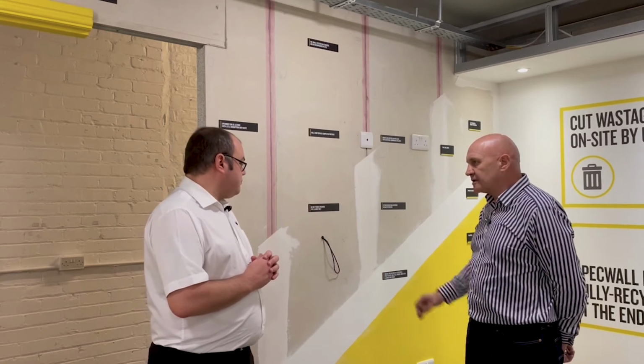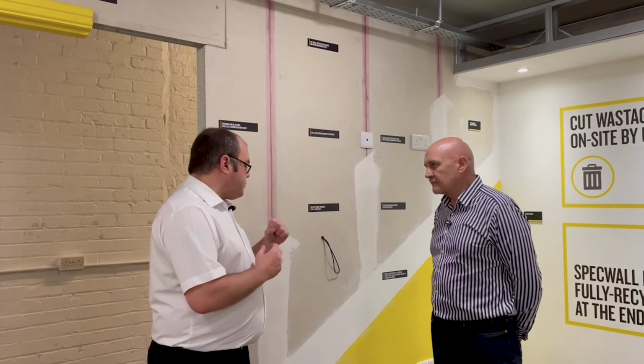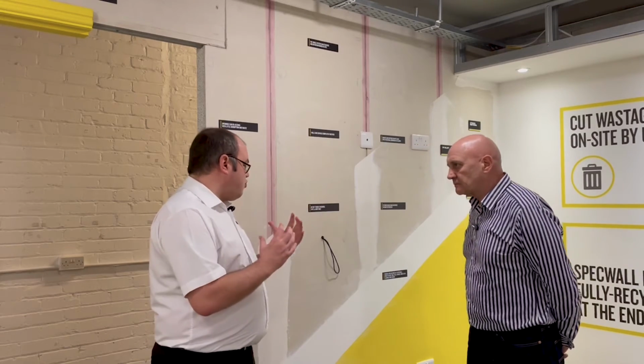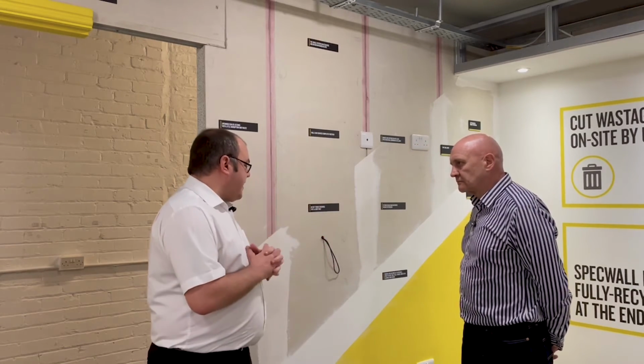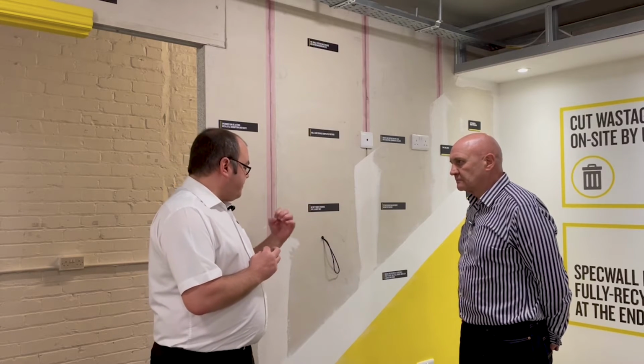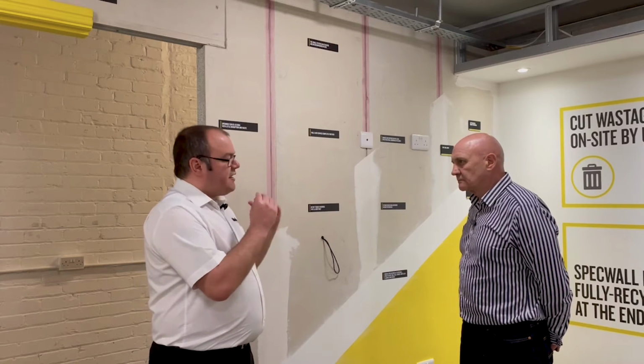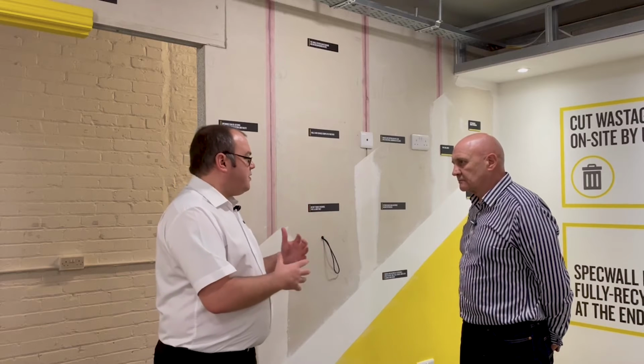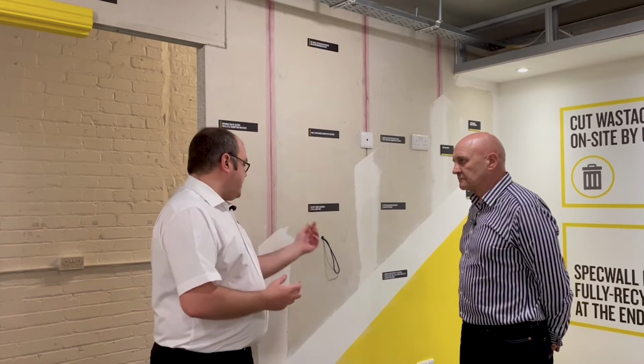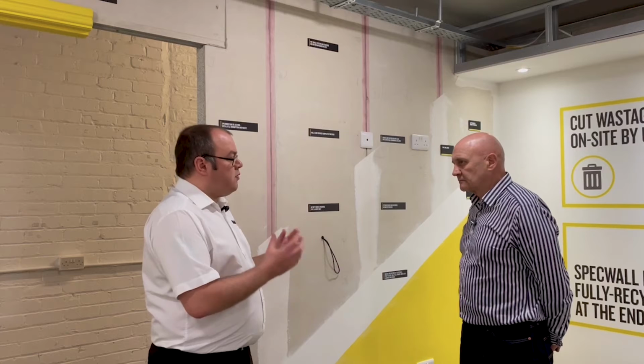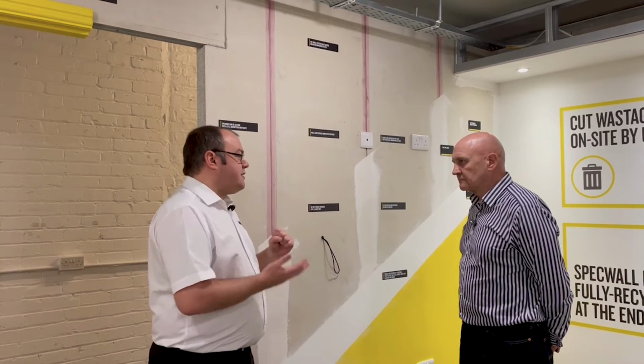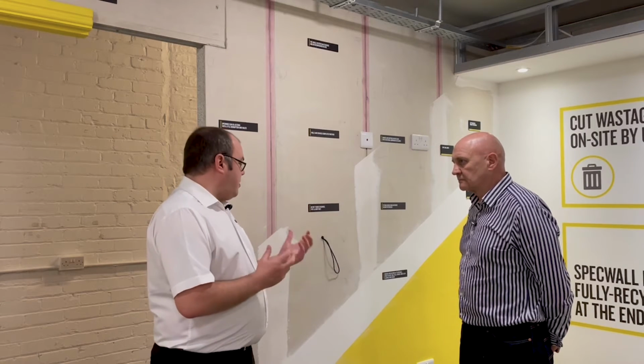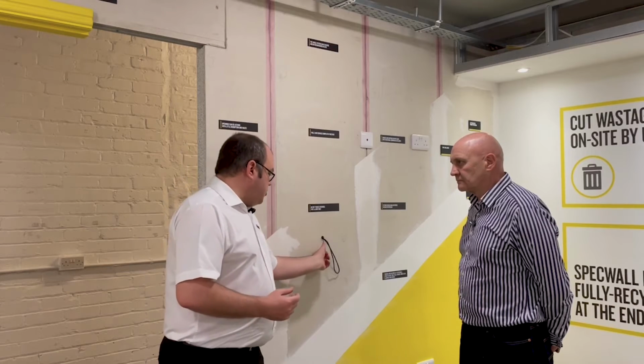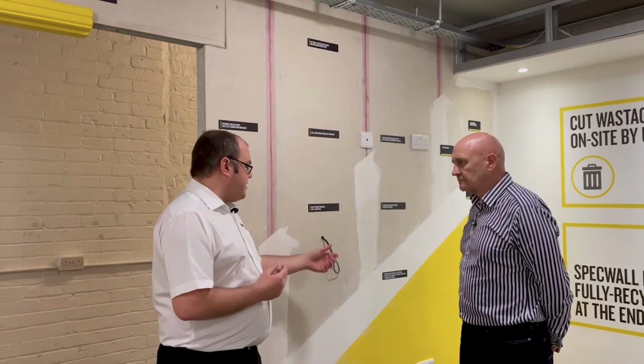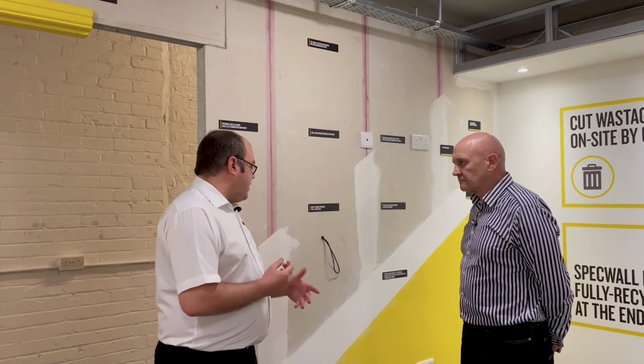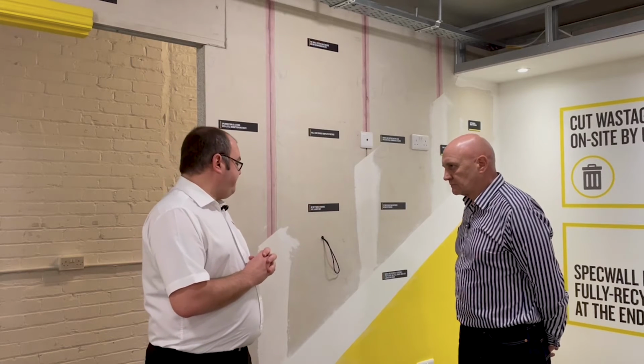Can they bunch the cables? Yes, provided it's within the spec on our drawing, they can follow that. Under our test standard, even though it just says cable of a certain diameter, that covers any cable type - it could be a data cable or a telecoms cable, provided it matches the outside diameter. Typically we test 21 mil or less, which with these small penetrations is usually a data cable or similar, and that would be covered.